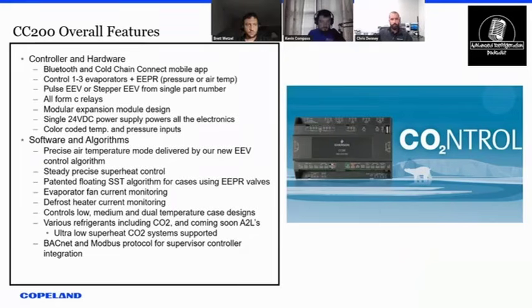So I'll go over some more features here. I mentioned the Bluetooth, pulse, stepper, and EEPR, all from one part number. We don't have any other case controller right now in the catalog. So this kind of brings all those features together in one part number. We feel that's an improvement for us because then you only have one part number to train on, one SKU to keep track of, instead of training across multiple part numbers and worrying about how many pulse, how many steppers do I have. Some manufacturers split it up by coil. So this does 1 to 3 coils, all the valve types, all from one part number.